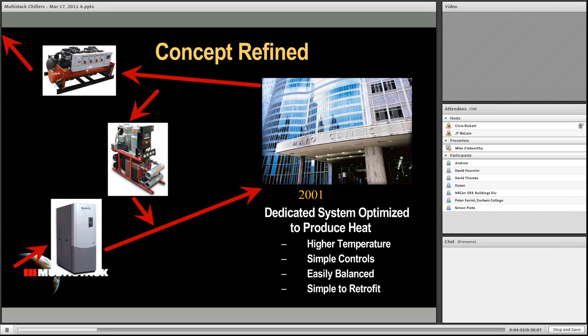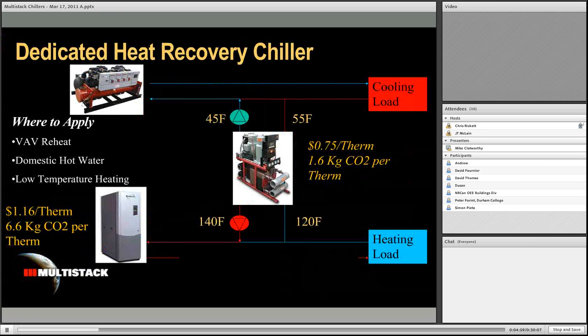We have refined the concept into something that we call dedicated heat recovery. And that's enabled us to produce higher temperature water, to simplify the controls, to make it easier to balance, and much simpler to retrofit. So this would be a schematic that shows a typical heat recovery application. It's not specific in terms of building type. Basically, we can recover heat and use it anytime there are simultaneous heating and cooling loads. And if you think about it, most buildings have a chiller running along with a boiler firing, and specifically hospitals, resorts, certain types of office buildings, all are candidates for that.